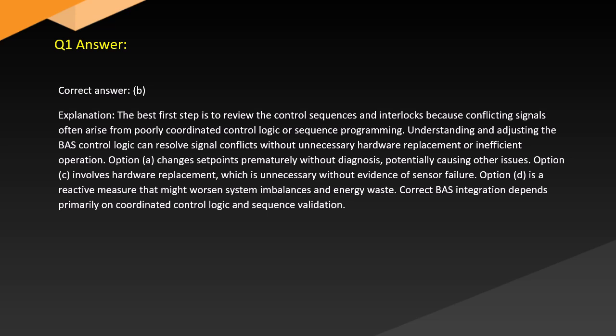Answer. Correct answer: B. Explanation. The best first step is to review the control sequences and interlocks because conflicting signals often arise from poorly coordinated control logic or sequence programming. Understanding and adjusting the BAS control logic can resolve signal conflicts without unnecessary hardware replacement or inefficient operation.